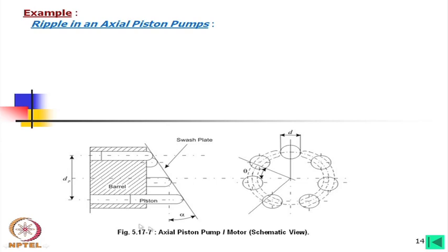An axial piston pump works as follows: the barrel is a cylindrical body with equispaced holes on a pitch circle — in this example, seven holes for seven pistons. The pistons slide on a stationary inclined plate called the swash plate. The tilt angle α can be kept fixed for a fixed-displacement unit or varied for a variable-displacement unit.